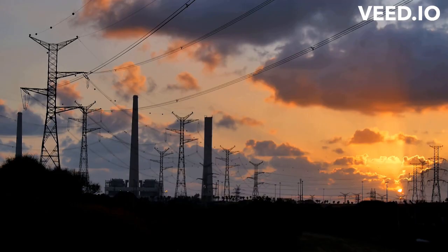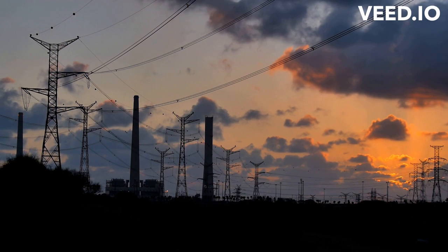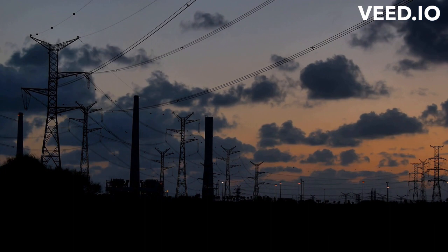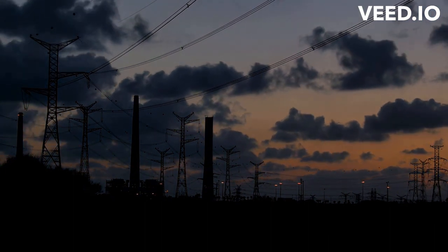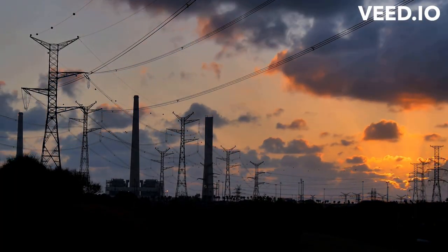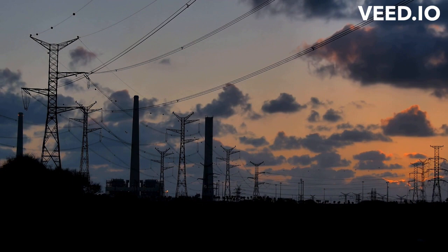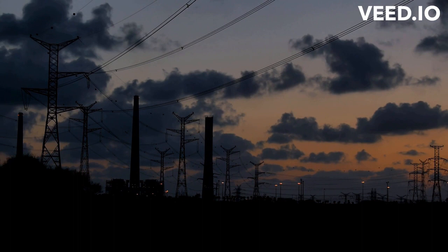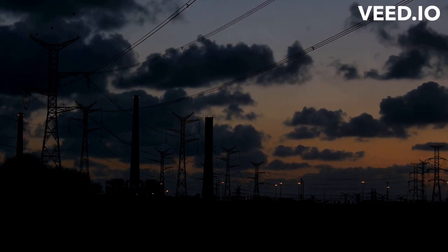Basic insulation, insulation of hazardous live parts. Supplementary insulation, independent insulation applied in addition to basic insulation. Double insulation, insulation comprising both basic insulation and supplementary insulation. Reinforced insulation, insulation of hazardous live parts providing a degree of protection against electric shock equivalent to double insulation. Whether or not any of the various types can be considered for safety purposes depends upon the circumstances and environment.